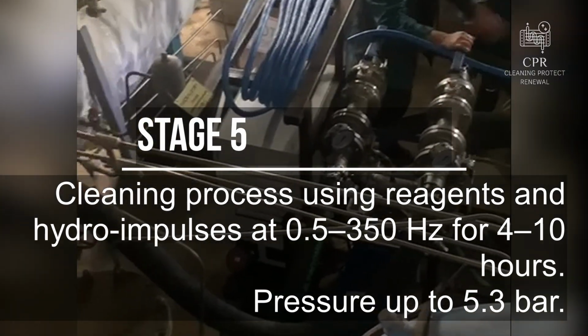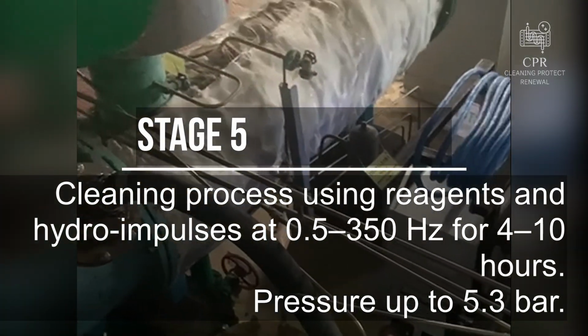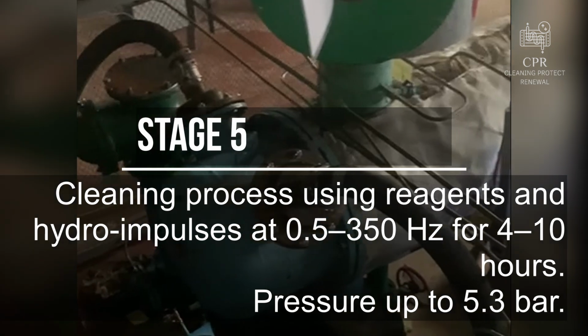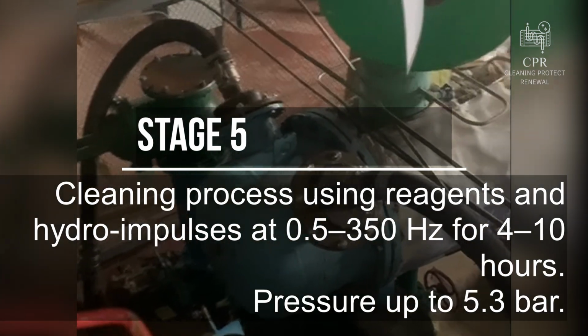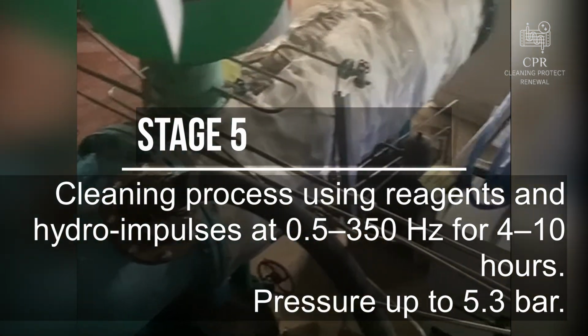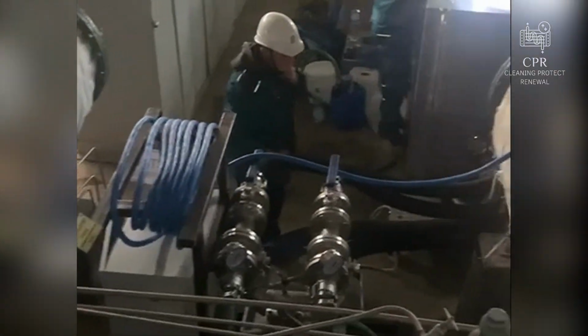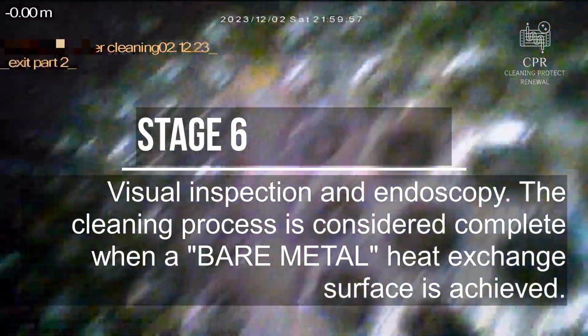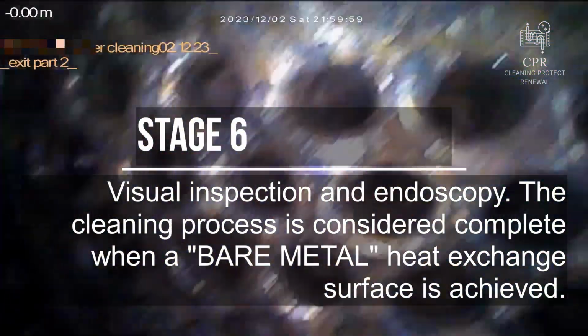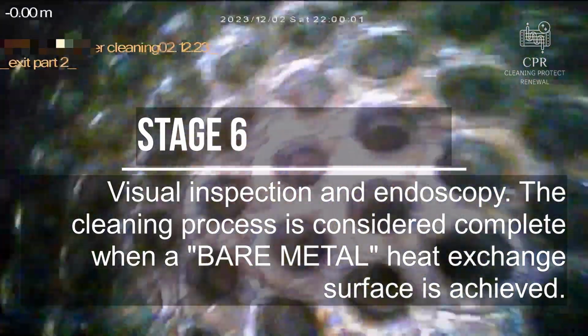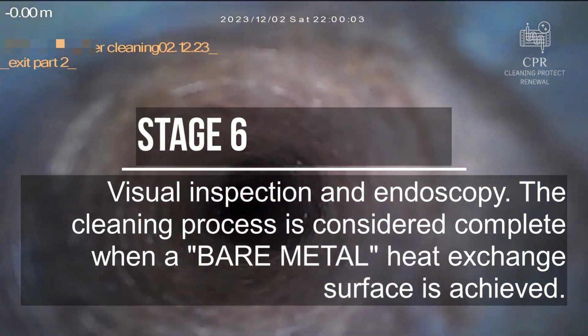Stage 5. Cleaning process using reagents and hydro impulses at 0.5 to 350 Hz for 4 to 10 hours. Pressure up to 5.3 bar. Stage 6. Visual inspection and endoscopy. The cleaning process is considered complete when a bare metal heat exchange surface is achieved.